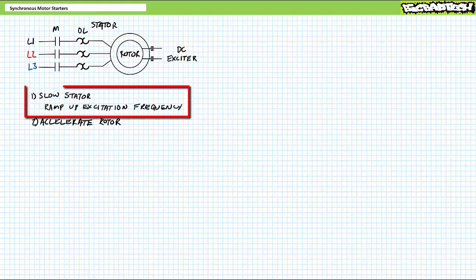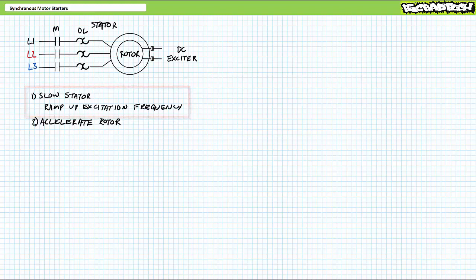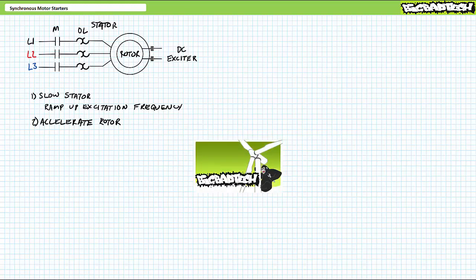Method one: slow the stator down. This method is especially apt for permanent magnet synchronous motors since their rotor field isn't capable of being de-energized or varied, but also works with electrically excited synchronous motors. Given an energized rotor at rest, rather than energizing the stator with a full voltage or direct online starter, one instead uses a variable frequency drive to slowly ramp up excitation frequency on the stator, so the rotor is afforded a gentle means of acceleration from 0 to 10 hertz, 10 to 20, 20 to 30, and so on up to the base frequency of 60 or whatever speed you want it to run.